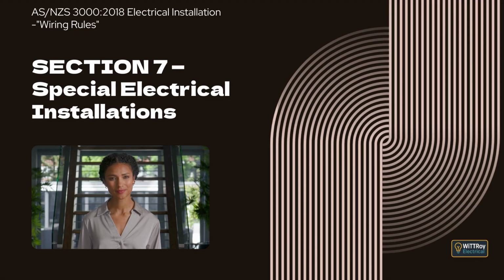Clause 7.2.9.3.2, segregation of cables. This clause explains that conductors supplying lifts must not be enclosed with conductors of different safety services or with conductors of any other wiring system. Clause 7.2.9.4, interposing switches. This clause explains that no switch is permitted to be installed between a main switch for lifts and downstream lift switchboards, except where an alternative supply system is provided or where switches are located remote from the building being supplied. Clause 7.2.9.5, switchgear.